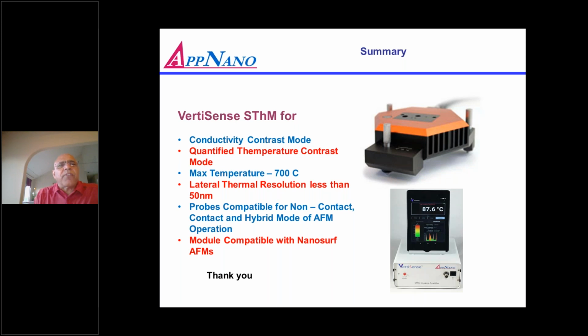customers have used different ways to do that. So you have to have a calibration standard and see the change in the voltage on the same sample, same place. It can be done, but it requires more. We don't have the process, but it can be done. The probe and the unit are compatible, and they can do it. It can do the quantified temperature contrast mode. You can measure the actual temperature if you calibrate it. The maximum temperature which we have seen can go up to 700 degrees Celsius, and the lateral thermal resolution we have seen is 20 nanometers, but regularly we can see 50 nanometers.